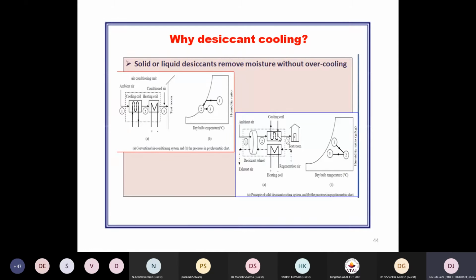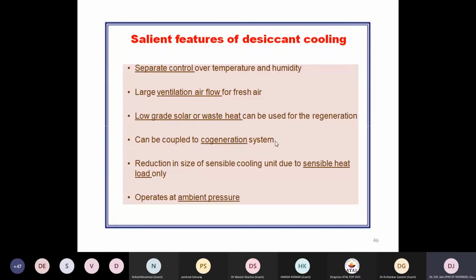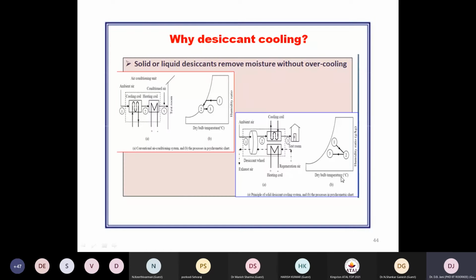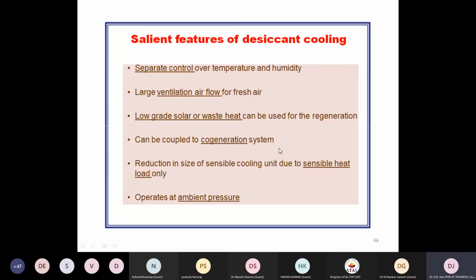Here, if the humidity is in range, but typically to meet the temperature you may constantly keep the evaporator running. But here it is a split, separable condition. Either component can be put off according to need and requirement. A large ventilation airflow supply of fresh air will maintain the necessary indoor air quality standard. Low-grade heat can also be used instead of high-grade electricity. It can be coupled to a cogeneration system. If large waste heat is available, it can be used for regeneration. So it may be coupled to a cogeneration system to maintain sustainable use of energy.